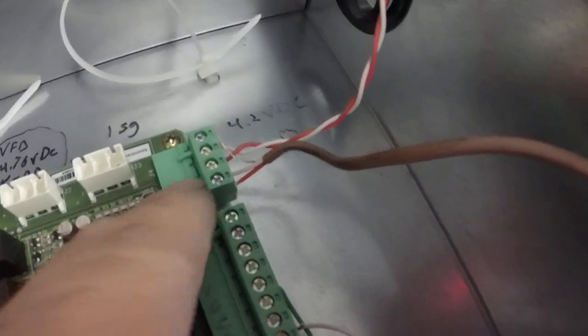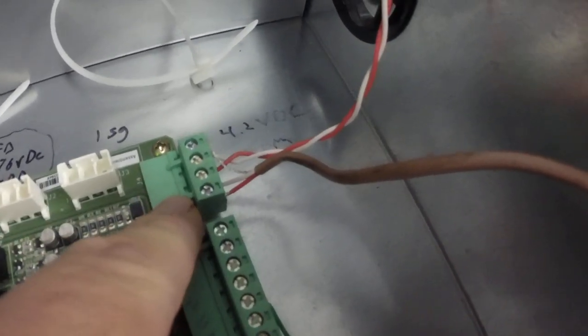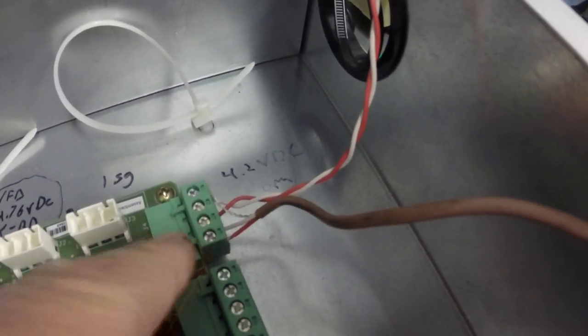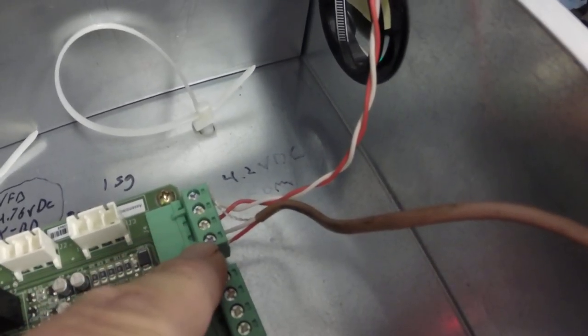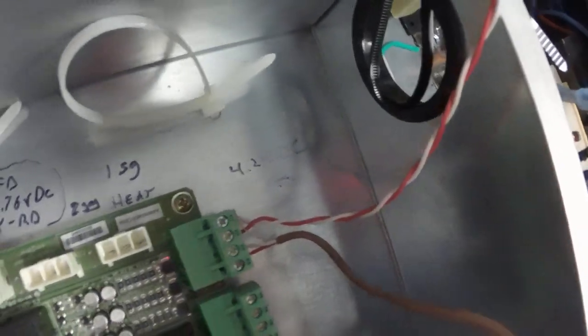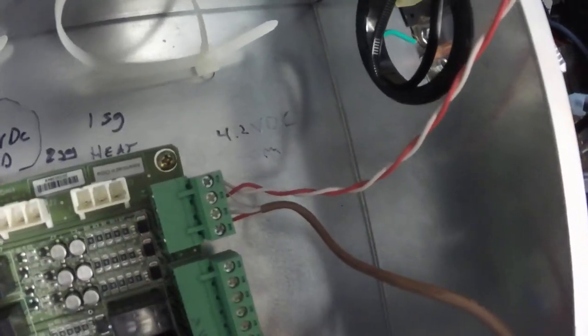I've got a small jumper wire that runs internal to this. Feeds power to the IMC. So 24 volts go into that pin one and two. And then we've got the other end of our twisted shielded pair on three and four.